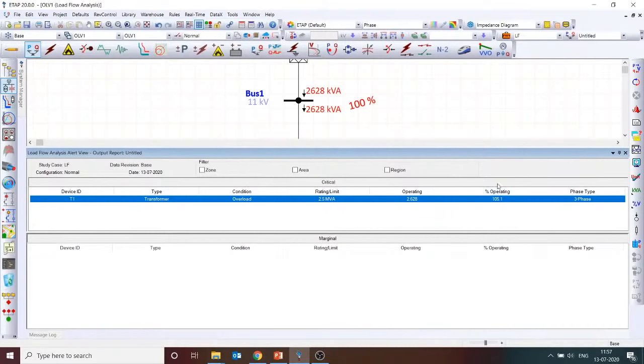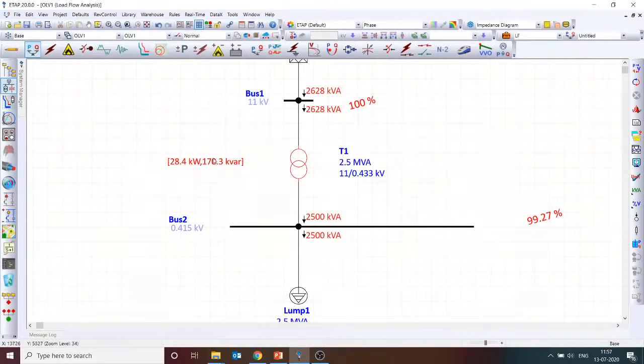So why is it overloaded? The simple reason is the transformer losses. When we say transformer rating, the transformer has a high voltage winding and a low voltage winding, and both windings are rated only for 2.5 MVA. You have loaded the LV winding with 2.5 MVA, so there are some losses, and the HV winding is loaded with more than 2.5 MVA. That's the real reason why the transformer is overloaded.